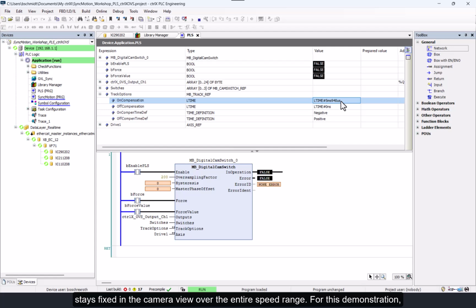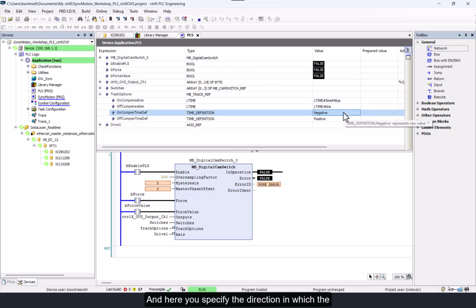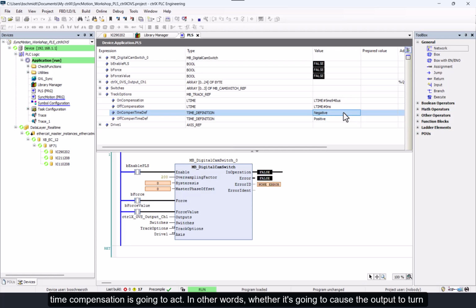For this demonstration, I found that I needed almost 6 milliseconds of on compensation to keep the captured position in the drive aligned with the on position of the PLS. And we'll take a closer look at this later in the demonstration. And here you specify the direction in which the time compensation is going to act. In other words, whether it's going to cause the output to turn on earlier or later than it would by using position alone.